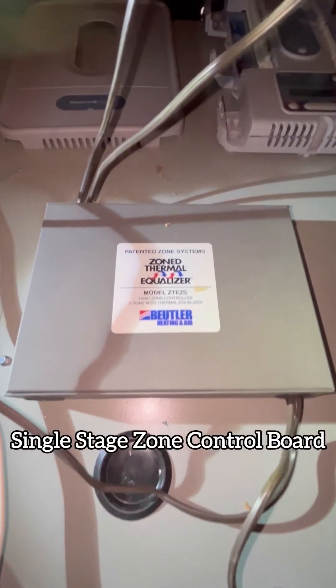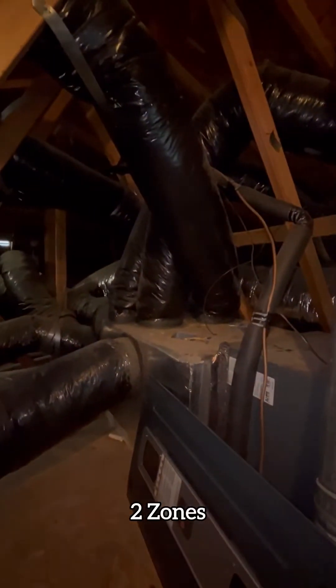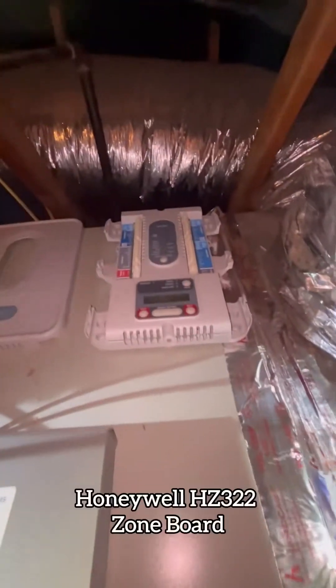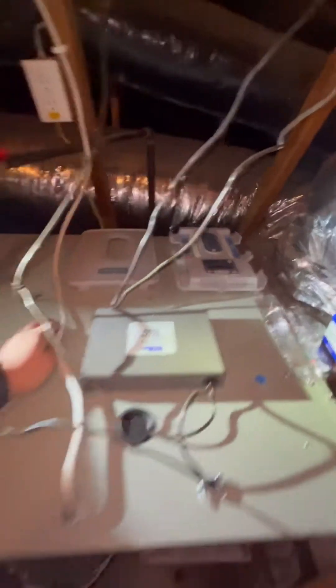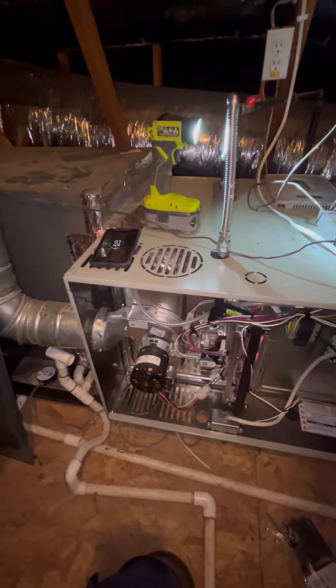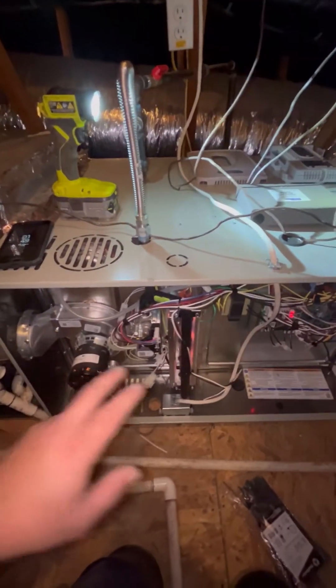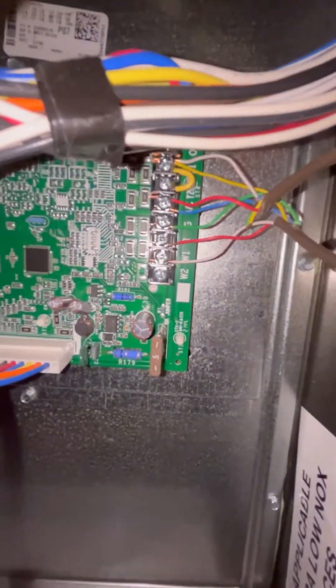I have a single-stage zone board but two-stage equipment and two zones, so we need to have the right circuit board. We're going to go with the HZ322 and use proportional zoning, putting it into second stage when both zones are calling for heat. Right now it's just running in low stage and there's no W2, so let's get it in.